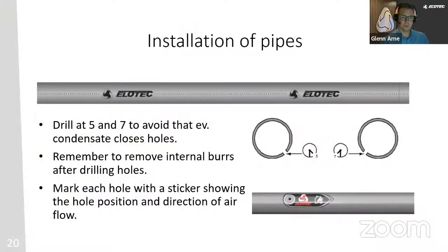And some of you also do the installation of the pipes. As I said earlier, remember to drill at 5 or 7 o'clock to avoid condensation closing the holes. Because if there is some water inside the pipeline, it will clog the hole. So always remember to drill the hole at 5 or 7 o'clock. Also remember to remove internal burrs after drilling the holes. Then you can use a smaller drill bit to remove the burrs inside the holes. And also remember to mark each hole with a sticker showing the hole position and the direction of the airflow. In that way, it will be much easier to find the holes when doing service on a later occasion. And you also see which direction the air will flow.